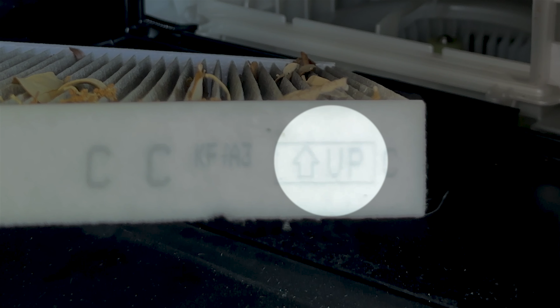And here's where I always start trouble on the internet. The OEM filter says up and has an arrow that's pointing upwards, hence that's how you install it. And because the debris was on the top of the OEM filter, it's letting you know that the air is flowing from the top down. All of this to say that when you put this filter in, those arrows will be pointing downwards.